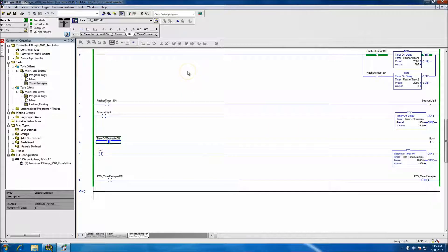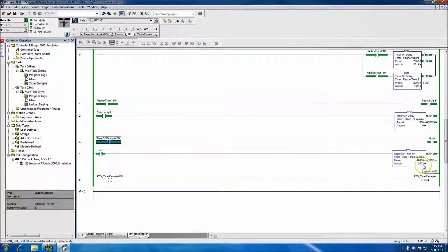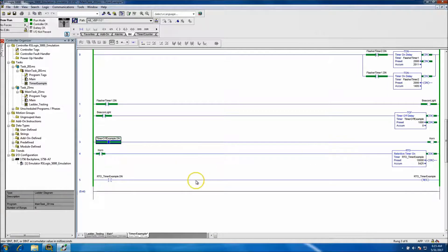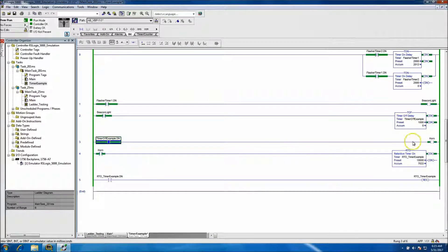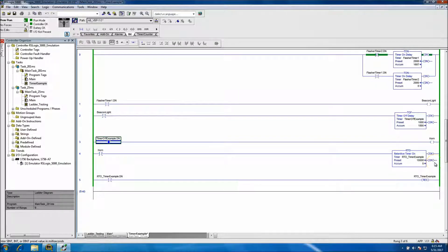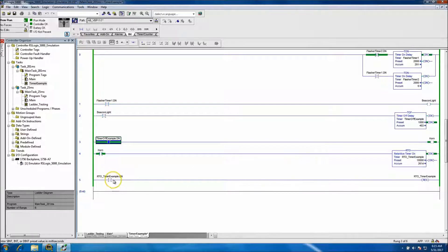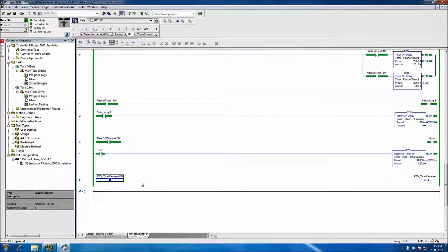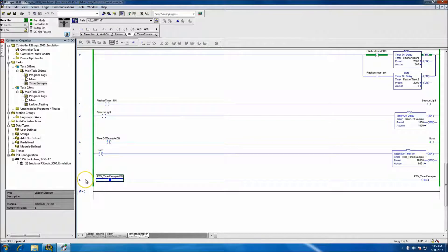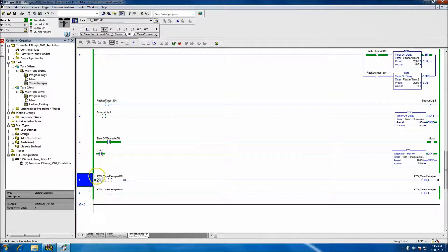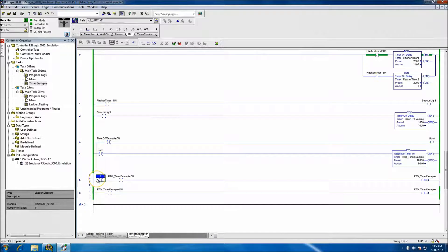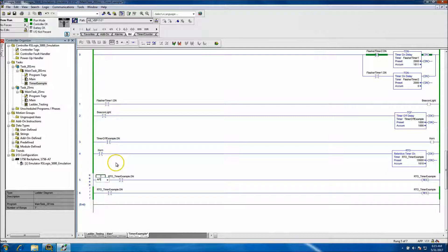If you see right here, the timer is going to stop every time the horn stops. The timer is going to stop and it's not going to be done until it reaches 10 seconds. Then when it reaches 10 seconds it resets itself. I can show you that by AFI'ing that real quick. If I AFI'd that, it did not let it reset.